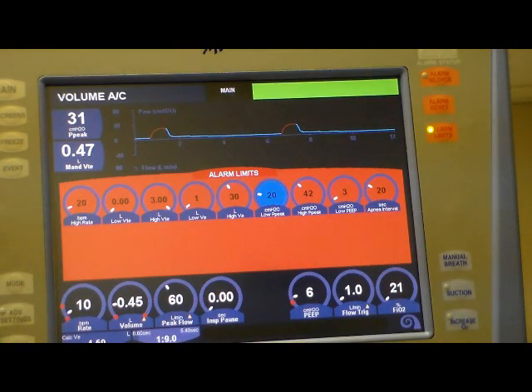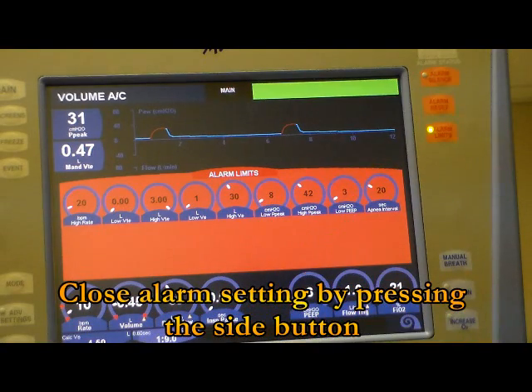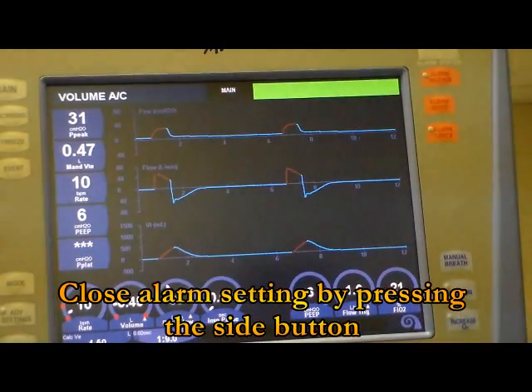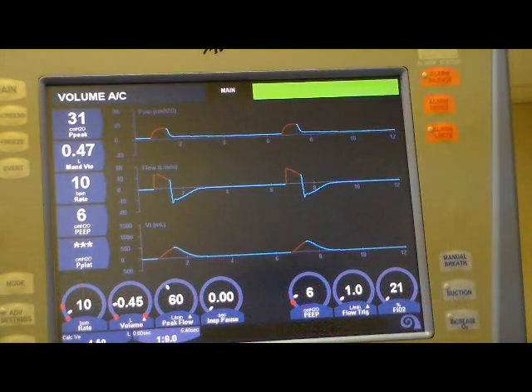Low PEEP, we have PEEP of 6. That's good. Usually about between 5 and 10, but we're at 6, so 3 is fine. And then apnea interval of 20-second apnea is pretty acceptable. Okay, so we're happy. Let's press that, and now we're into the ventilation mode.